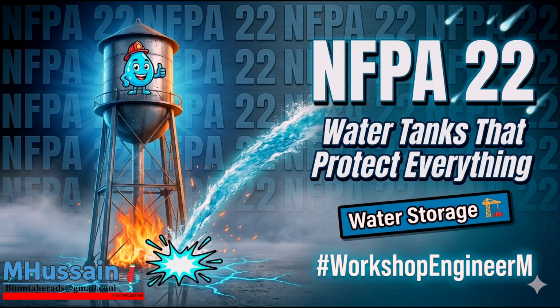Right, and if you mount it too low? Say 2 inches off the bottom. The cross-sectional area between the edge of the plate and the floor becomes so small that you induce massive friction loss. The fluid velocity skyrockets, the pressure drops, and you starve the pump. Which again causes cavitation. 6 inches is the mathematically proven sweet spot. It provides enough cross-sectional area for the water to flow horizontally without starvation, while minimizing the volume of dead water left at the bottom. That is a perfect example of a static piece of metal solving a highly complex dynamic fluid problem. And the 2023 edition actually updated the tank sizing requirements to ensure that these fluid dynamics are considered even earlier in the design phase.